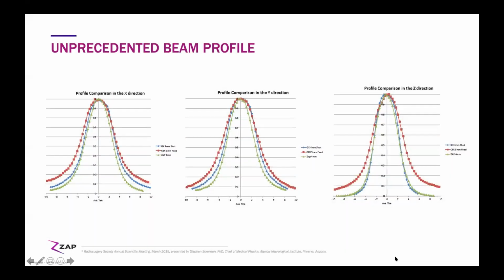Well, here's an example. This comes out of BNI, our flagship first customer, and they did a beam profile across multiple different devices, ZAP-X, Gamma Knife, and CyberKnife. And you can see that this is just one specific collimator, 4 millimeter collimator, where the differences are probably easiest to measure and most significant. But you can see that the steeper the dose gradient, obviously, the better the treatment for small targets.